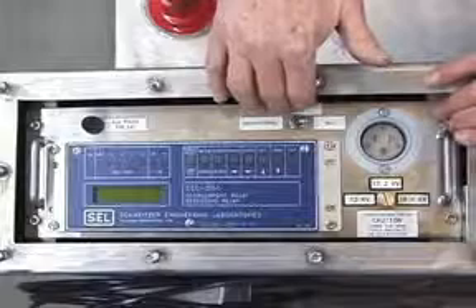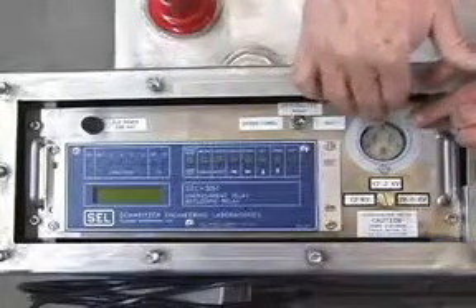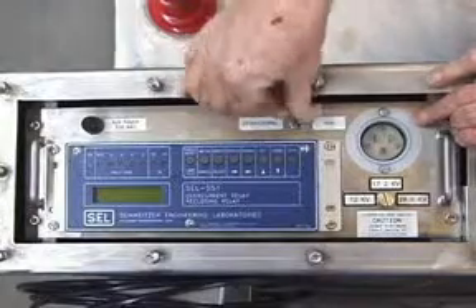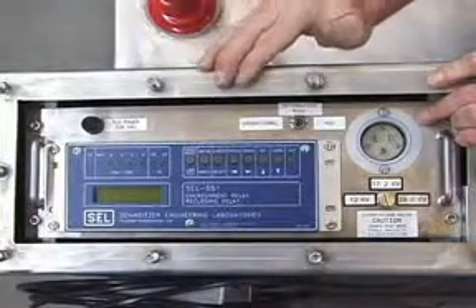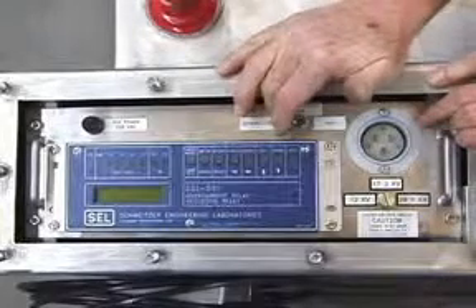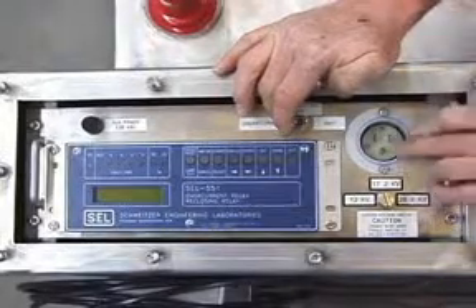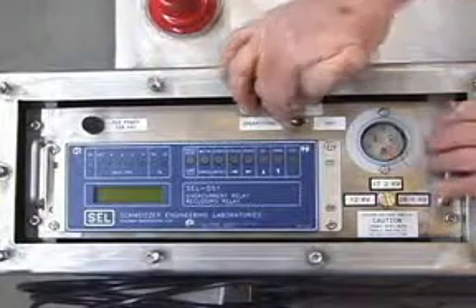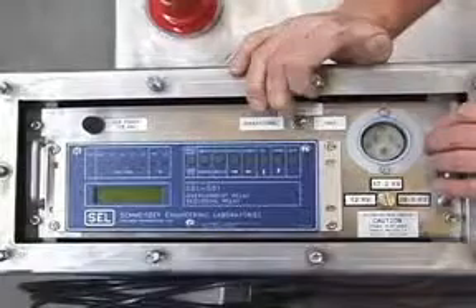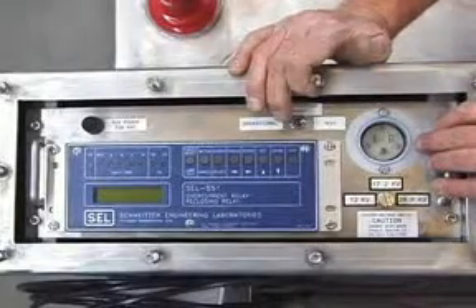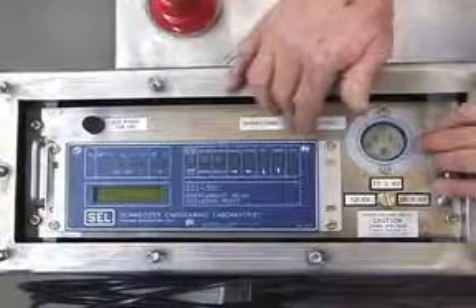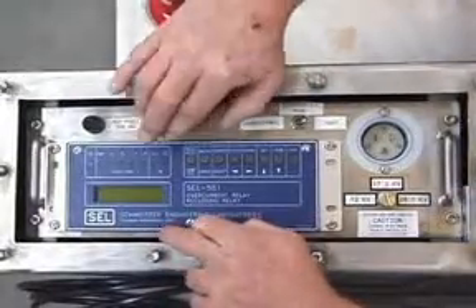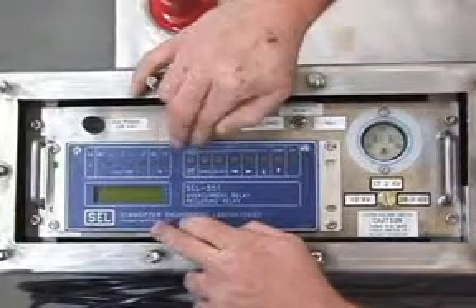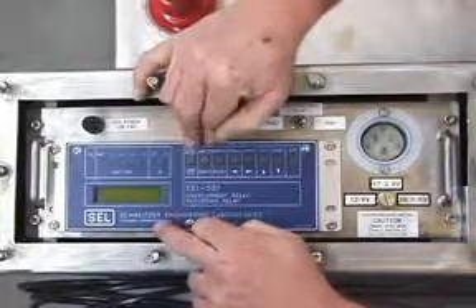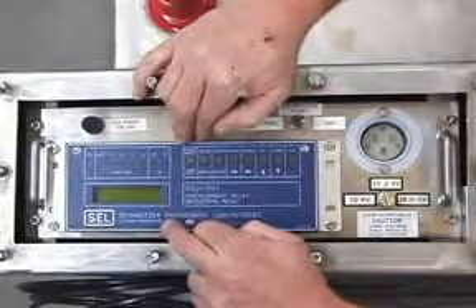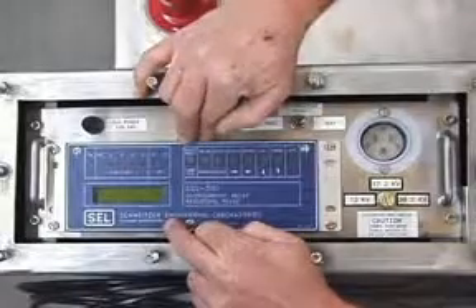You'll notice in this compartment that we have a 120 volt receptacle and a toggle switch that takes us from a test mode to an operational mode. What we've done here is we've created a system that allows the owner of the equipment to apply 120 volts AC shop power, put the equipment in a test mode so that you take the PT off the circuit and not backfeed your 600 amp bushings. And with that 120 volts, it allows him to power up the relay, do the relay settings, test the system, including a full trip function test right there in the yard before it goes out to the field for installation.